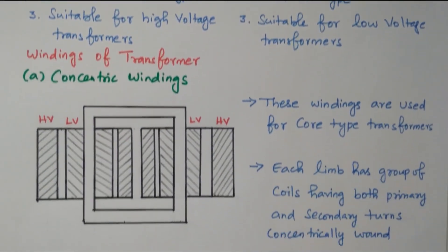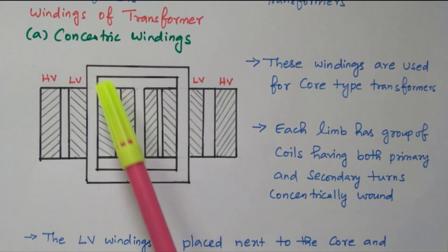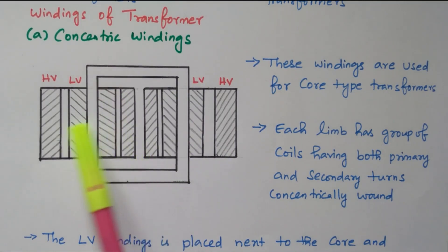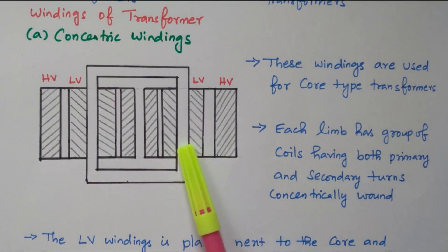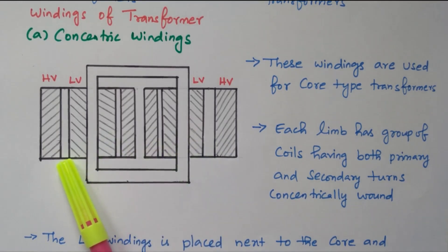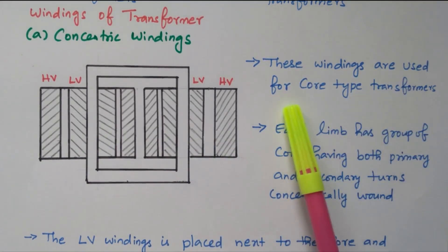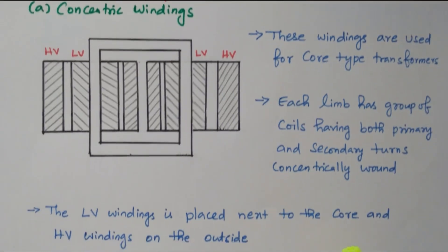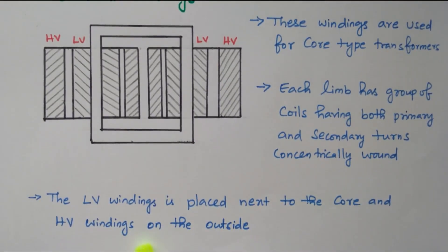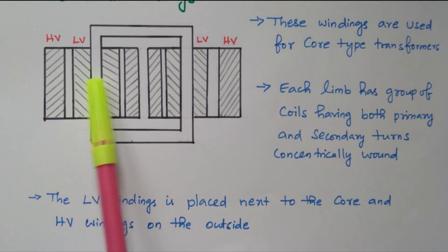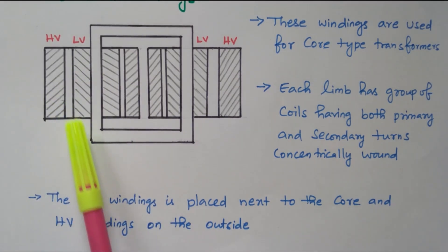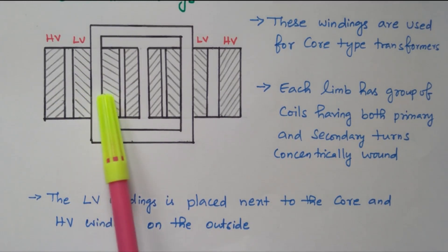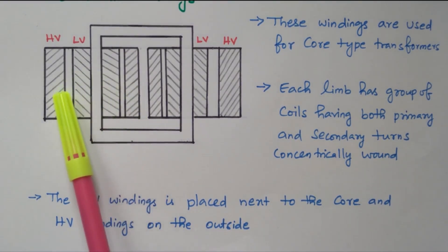Now we will see the winding types: concentric winding and sandwich type. In concentric winding, the low voltage winding is placed on the core and the high voltage winding is placed on the outside over it — on both sides. This is used for the core type transformer. Each limb has a group of coils having both primary and secondary turns concentrically wound. The LV winding is placed next to the core and the HV winding is on the outside.